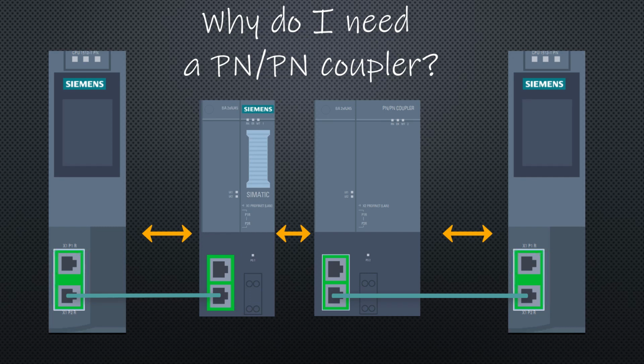This makes a PN/PN coupler really useful when you want to talk between identical cells, for example, as both sides of the coupler can actually be using the same address range, which equates to modularity of design. But also, as it's just the predefined transfer areas that get passed between the cells, a PN/PN coupler can actually serve as a security device, not allowing any other sort of comms to pass through.